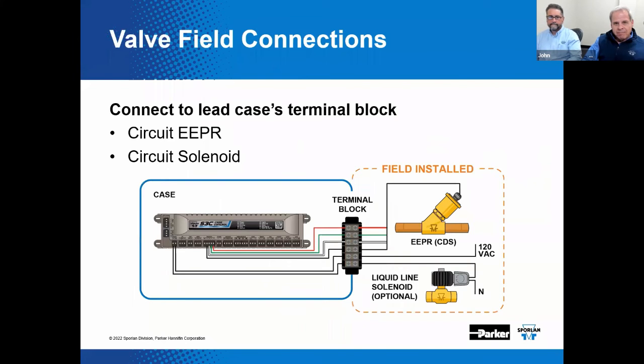Eventually. Now, here's, as I promised, some more detail regarding wiring of the liquid line solenoid valve and the EEPR. In this case, we show the EEPR being terminated directly on the case control. Now, how can we get away with that, John? Well, the case control can be configured to handle this installation if thermostatic expansion valves are being used and not EEVs for superheat control. So this would be a situation where a TEV is being used instead. So there'd be an intermediate terminal block to facilitate the connections to make it simple.